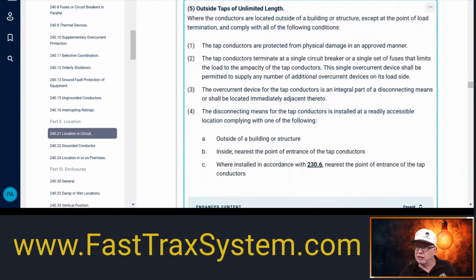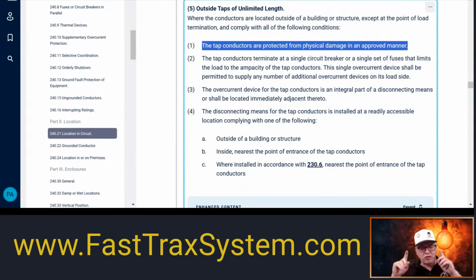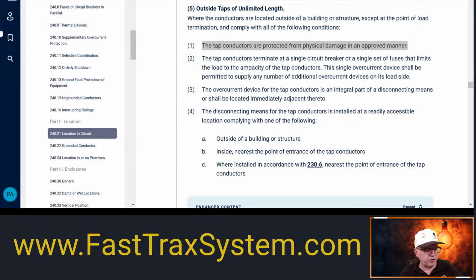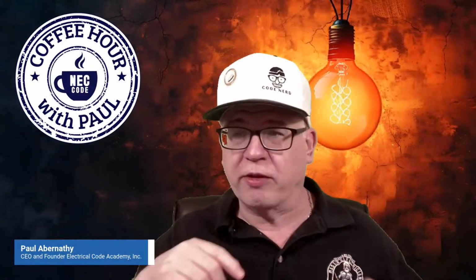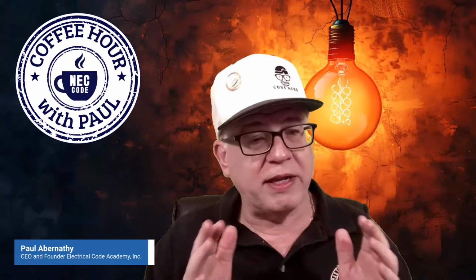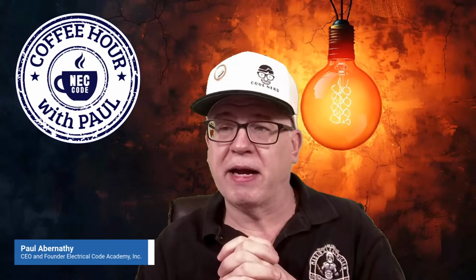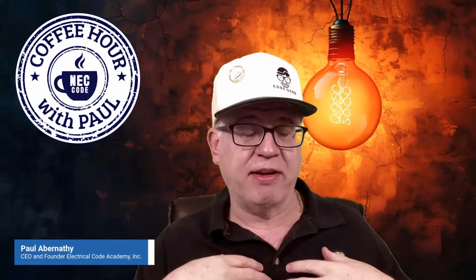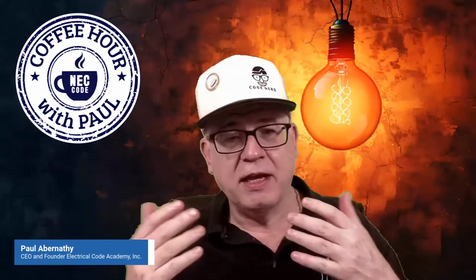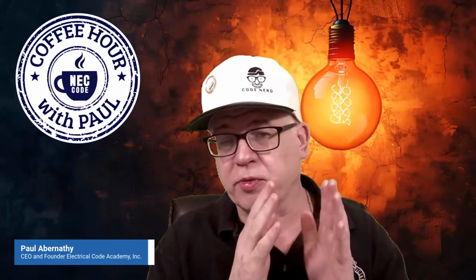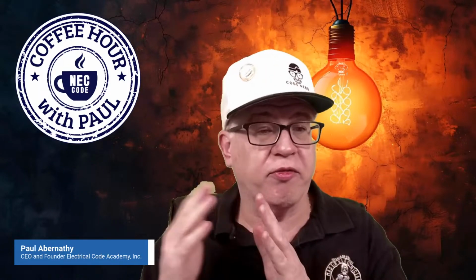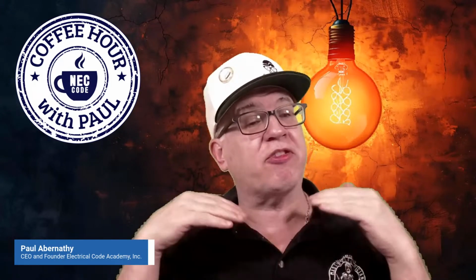Number one, the tap conductors are protected from physical damage in an approved manner. Now, you do see that this runs all over the place, folks, whether it's the 10-foot rule, the 25-foot secondary rule, or the feeder tap rule. Some say an approved raceway, some say whatever. It goes all over the place, so there is no defined uniformity to this. I would hope somebody would submit that to the code making panel to try to bring unity. Do you want the conductors in an approved raceway, or is it okay in an approved manner? Again, this one is probably a little more lax because it is outside of the building.